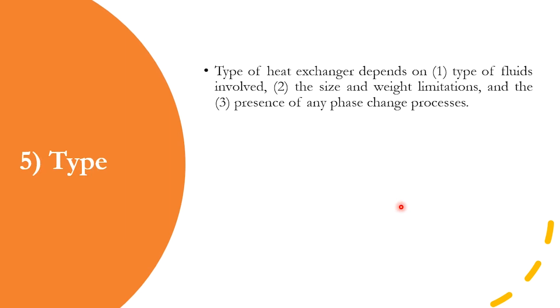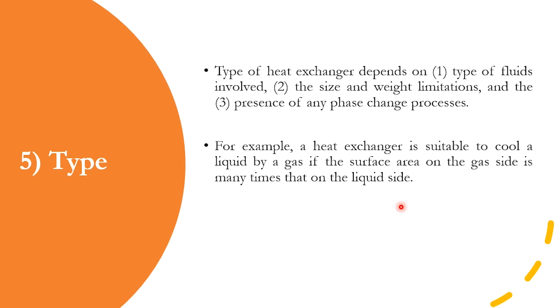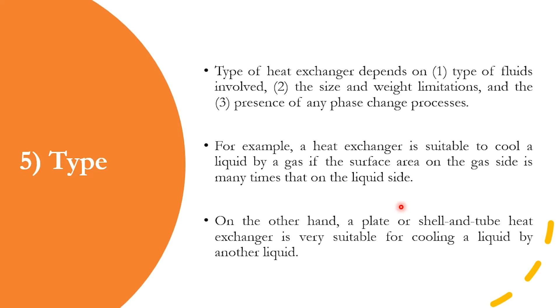Number five is the type of heat exchanger, which is dictated by three main factors: the type of fluids involved (whether corrosive, viscous, liquid, or gas); size and weight limitations; and the presence of any phase change process — because in phase change, an additional parameter h_fg (enthalpy or latent heat of vaporization) must be included. For example, a finned-surface heat exchanger is suitable to cool a liquid by a gas if the surface area on the gas side is many times that of the liquid side. A plate or shell-and-tube heat exchanger is very suitable for liquid-to-liquid cooling.